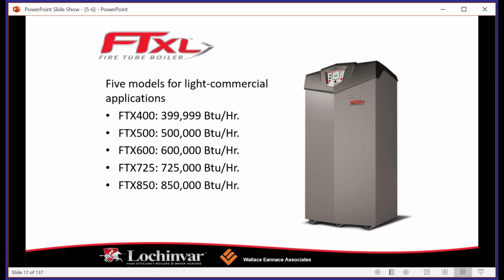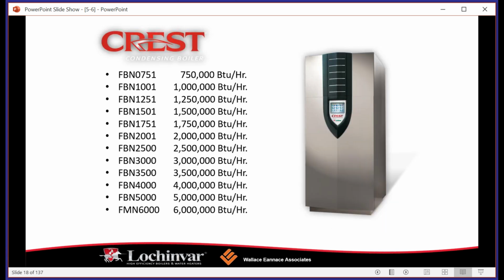Now we do have some crossover here, right? 850,000 BTUs, 725,000 on the FTXL. And we have 750,000 and 1 million on the lower end of the Crest. Would you use an FTXL in place of a Crest? Well, it depends on your job. The Crest is going to have a bigger footprint than an FTXL. So again, if you're looking at an application where you've got a ton of piping to squeeze in, you don't have a big boiler plant, there's stuff there that's being decommissioned but not demoed, perhaps, the FTXL is going to be a great choice. Because again, you're going to be able to slide that in. It's a large filing cabinet sized piece of equipment. And you're going to be able to put all those BTUs into a very small space. So again, Crest condensing boiler is going to be CSD-1 compliant out of the factory. It's going to have all of your building automation controls standard. So again, this is the flagship line for our commercial stuff.